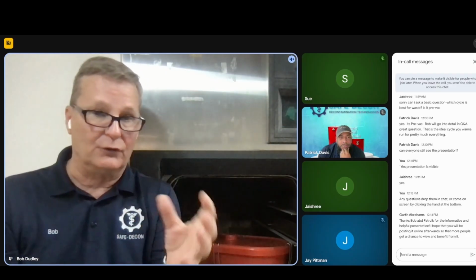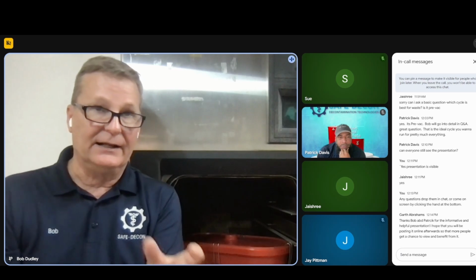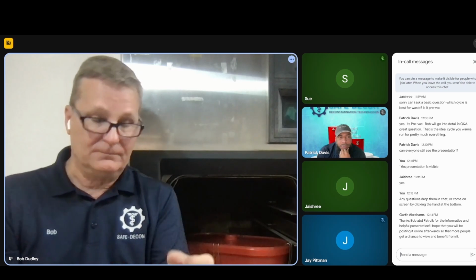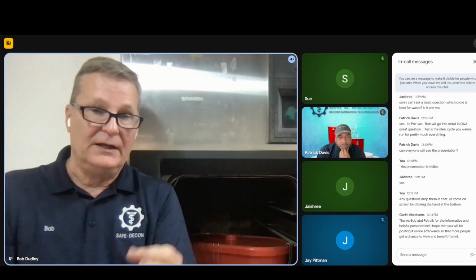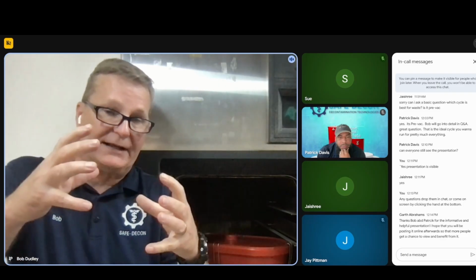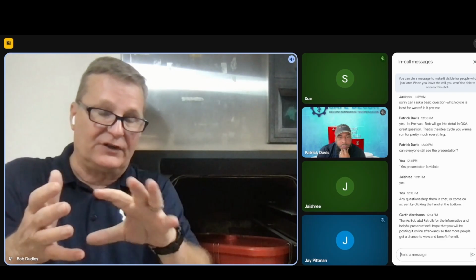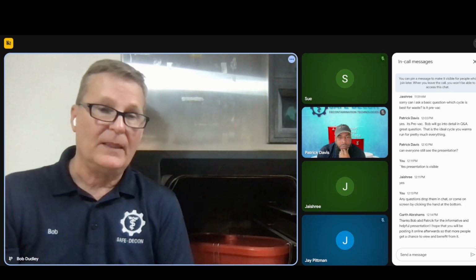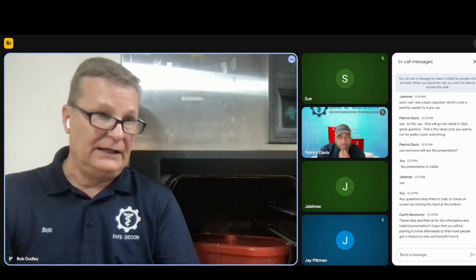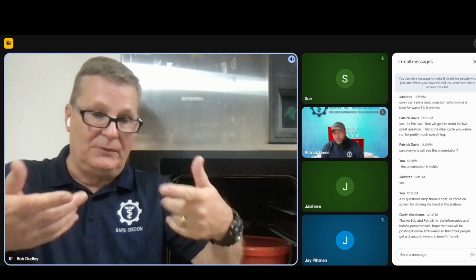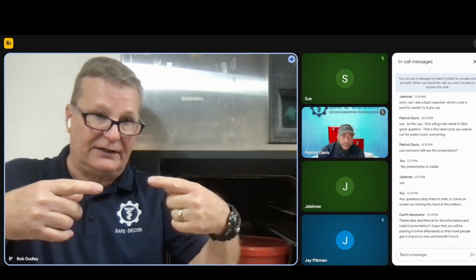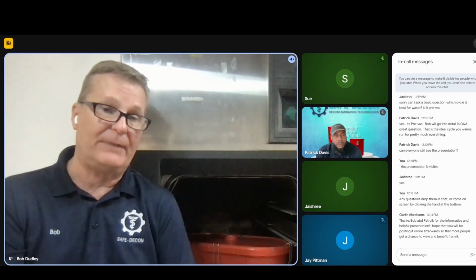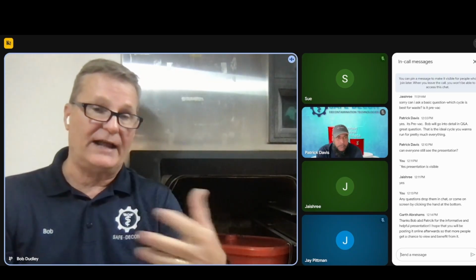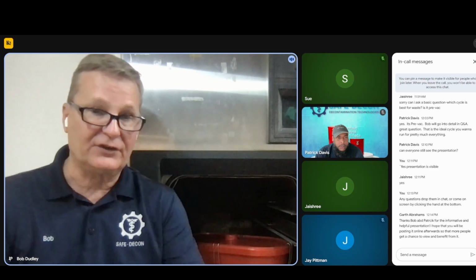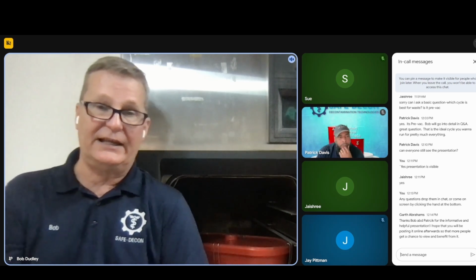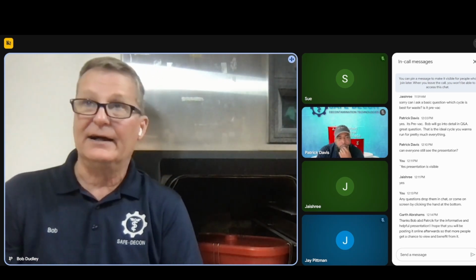But if that bag folds over in any way, it will hinder that heat and steam penetration. Now the bag's going to blow up, and then it's going to retract itself. When it does, everything shifts and that bag can fold over. The minute it folds over and it doesn't expand, and you pull the vacuum with the moisture content, it can actually reseal that bag shut, so that when it goes to pull the vacuum, it's not going to pull everything out. And again, during the results, you can see the amount of failures that I was getting.